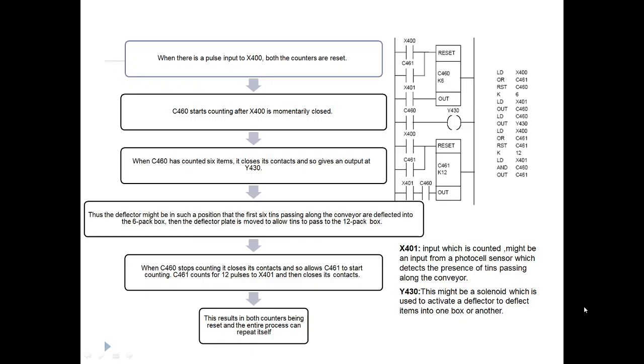With the pulse of input X400, both the counters are reset. Input which is counted might be an input from the photocell sensor which detects the presence of tins passing along the conveyor. Y430 might be the solenoid which is used to activate the deflector to deflect the items into one box or another.